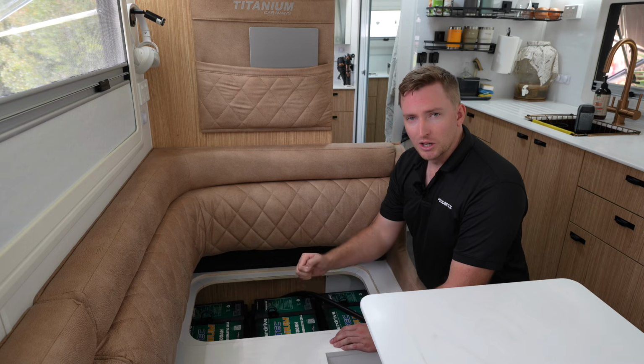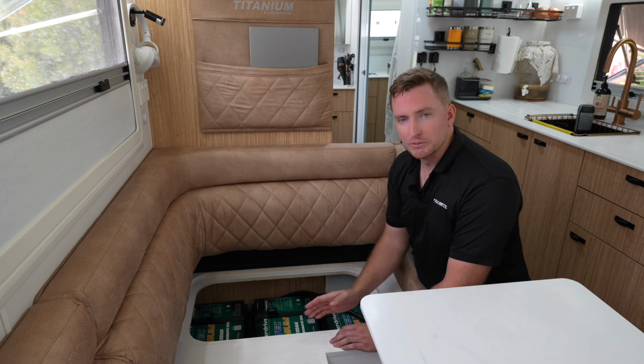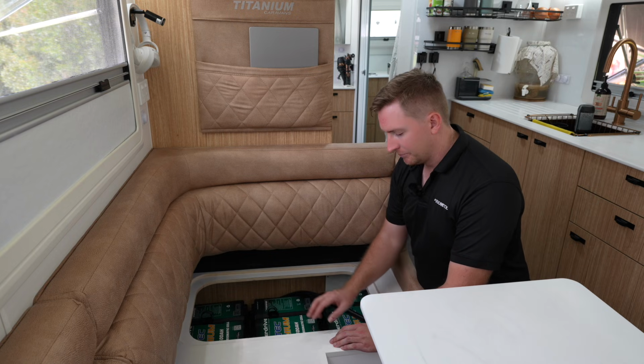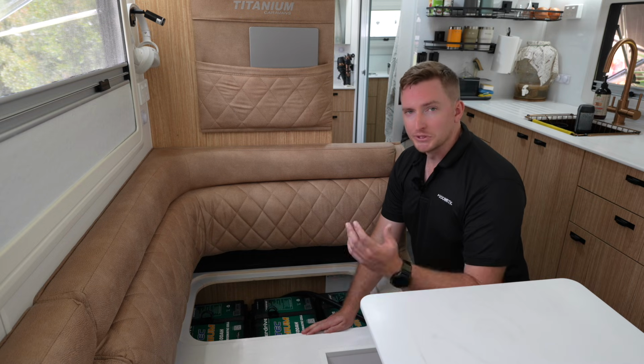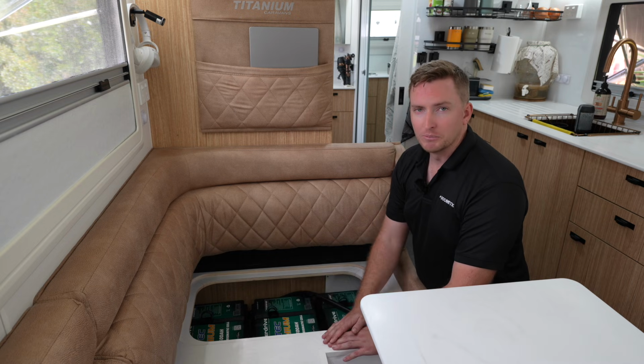Instead of it having the hole like we normally do, it'll just have a latch on top and a gasket seal that runs across the top here to make sure that that particular portion of this build is classed as gas proof. Now, you need to make sure that that lid is fixed down by tooling, so screws, bolts, etc. That's all perfectly fine.